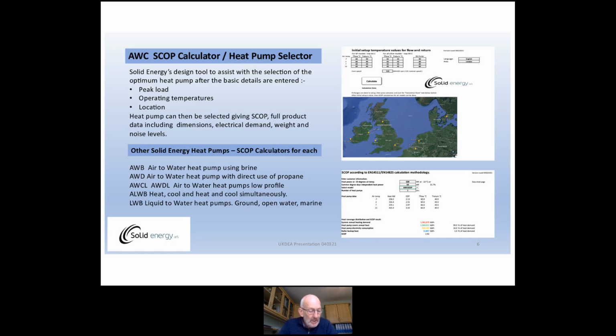To assist with the design of heat pump installations, we have our solid energy SCOP calculators. These are complex spreadsheets where we have to enter basic information such as peak load, operating temperatures, and location. The calculator selects the most appropriate heat pump, calculates the COP, and provides the basic data sheets for the heat pump selected. We also manufacture other air source heat pumps for different circumstances.